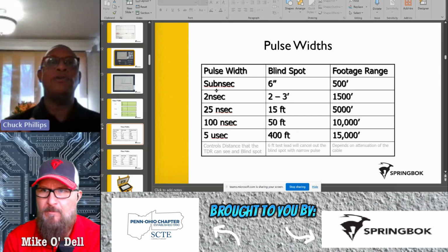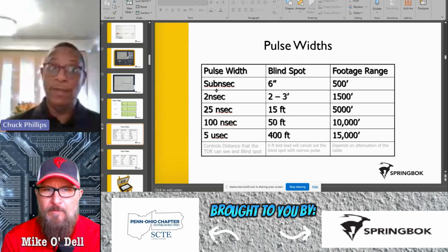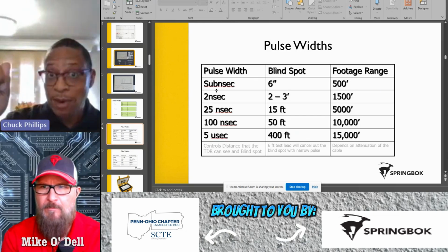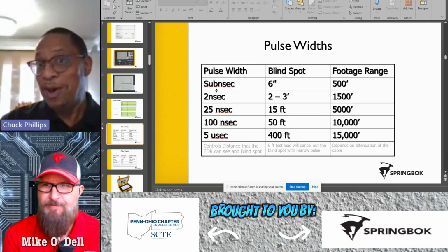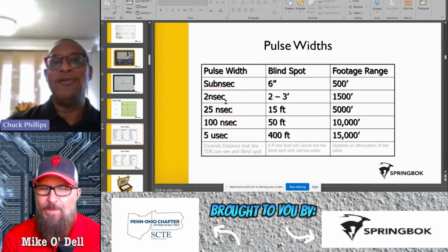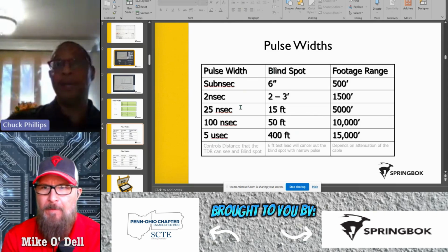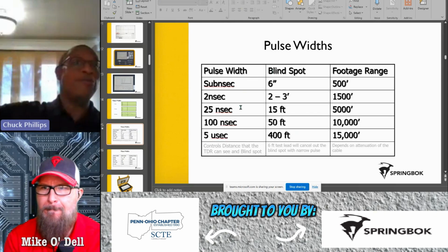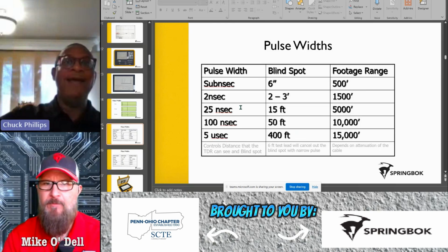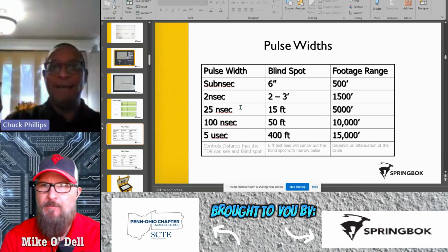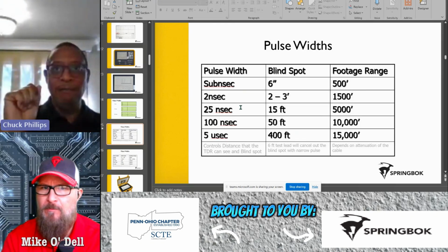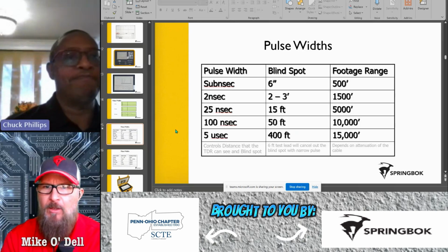I just mentioned it. Your squirrel chews, your nicks in the cable, your fresher water, which is harder to find than older water, by the way. So that's the other thing that you're paying for when your company invests in the $2,000 or the $3,000 TDRs. It's not just a distance thing. How small of a problem are you looking for? Does that make sense? Yeah, it does.